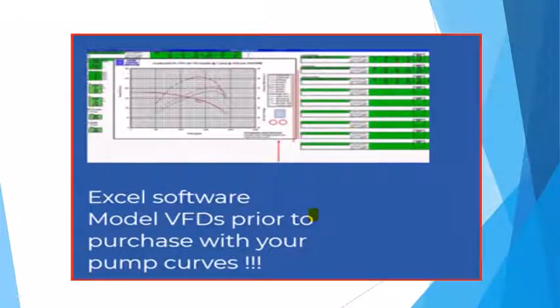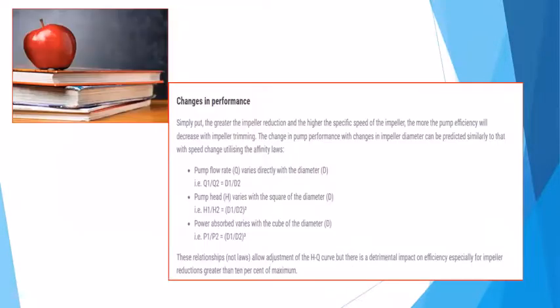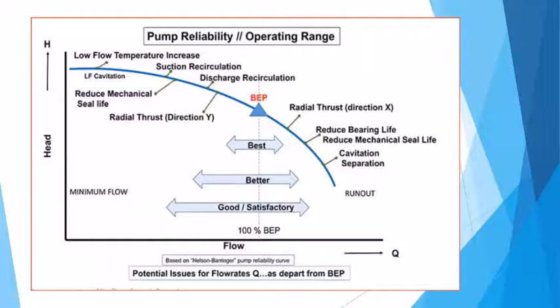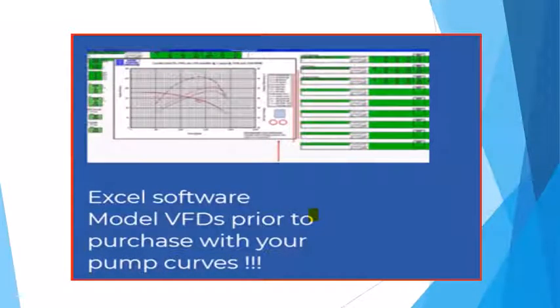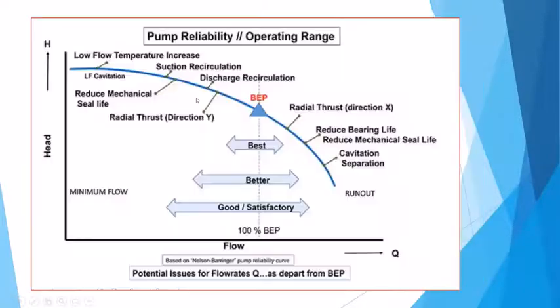So there's a piece of software available, by a fellow out of Australia with the Water Pumping Institute, that I have to recommend if you're doing VFD control. I'm going to go into a little bit how the VFD works in a couple of minutes. The pump companies normally will give you one curve for 1800 RPM. They don't show you that this best efficiency point does not slide linearly as you adjust the speed. A lot of people think, oh, I'm just slowing it down. Well, no, that's not necessarily the case, because that impeller may not pull as much water as it did before, and this curve, the best efficiency point, moves.